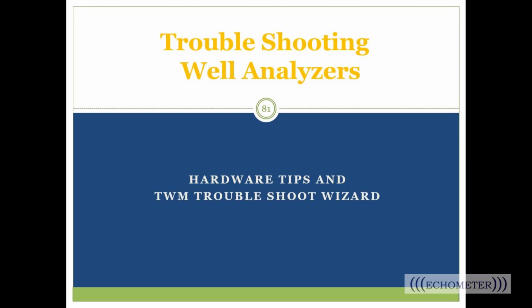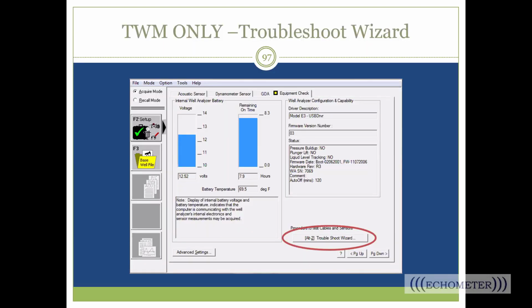Great. All right, I know we're running short on time, so I did want to talk just a little bit about the well analyzer. Many of you are using the well analyzer, both with TWM and with TAM. When it comes to troubleshooting the well analyzer in the TWM software, we have something on the equipment check tab called the Troubleshoot Wizard. That's the slide that you see here. When you're in the acquire mode of the TWM software and you go to the equipment check tab and you're connected to the well analyzer, you see the blue bars and the information. This is also where you can look if you're wondering what features your well analyzer has been licensed to use, as far as acquiring plunger lift data, pressure transient, things like that.